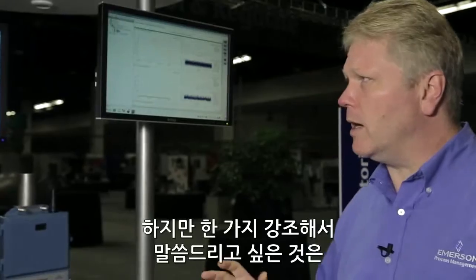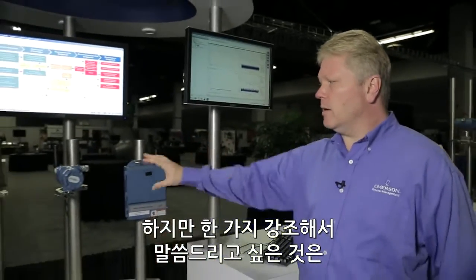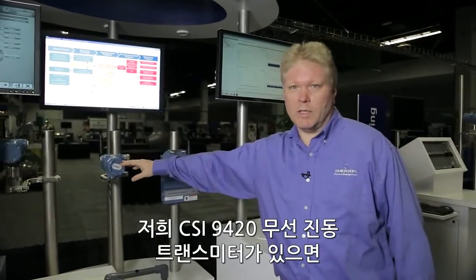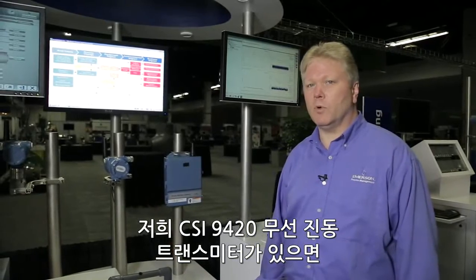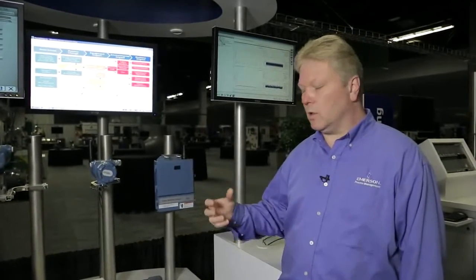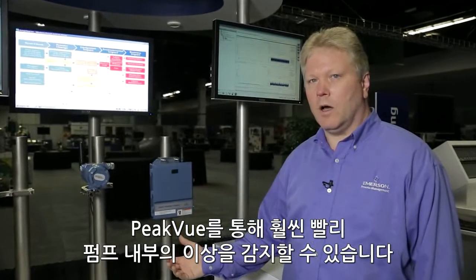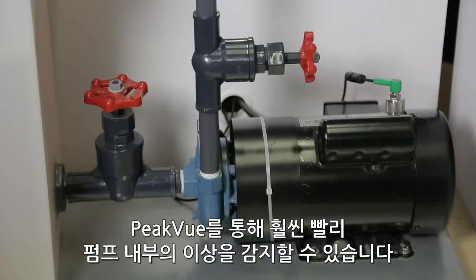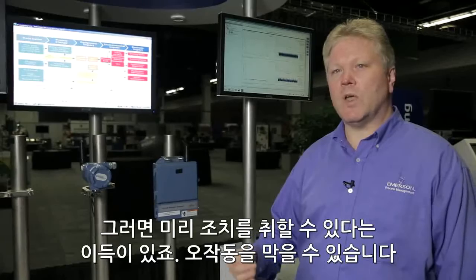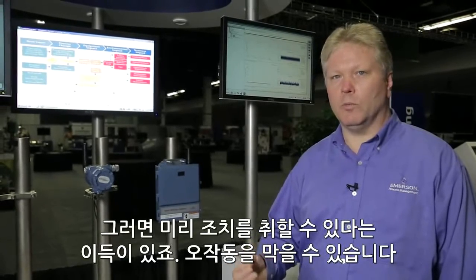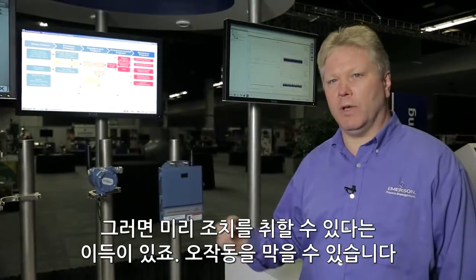The one key thing that I would like to say, though, is that our wireless vibration transmitter, the CSI 9420, has the overall vibration, but it also has Emerson's PeakVue. And PeakVue really gives us a lot earlier detection on a problem that's going on in the pump. So there's time to take action, and that's a real benefit, time to take action and prevent the failure.